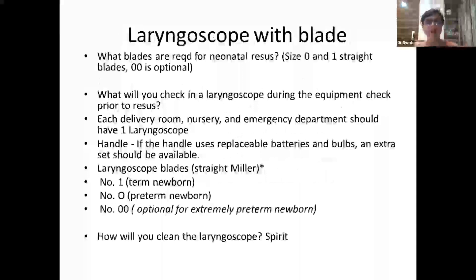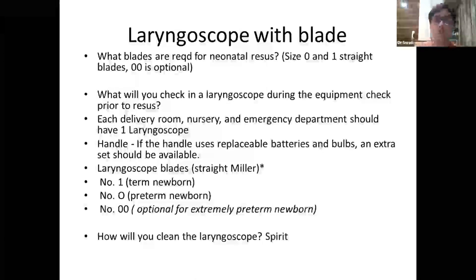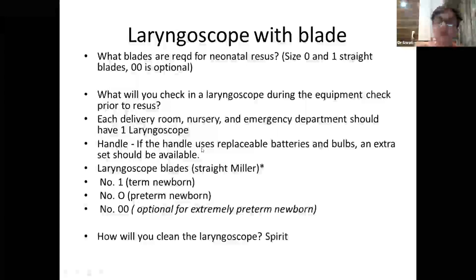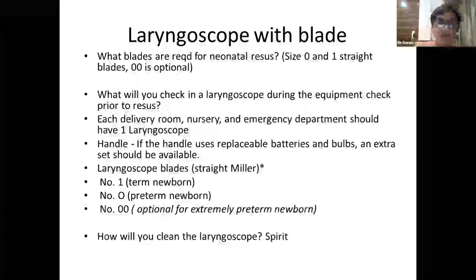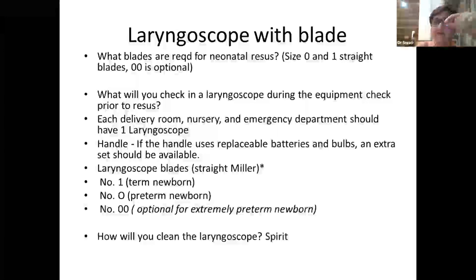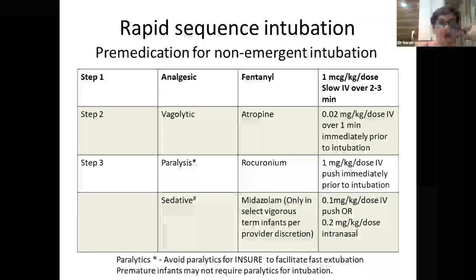For neonatal resuscitation, size 0 and size 1 straight (Miller) laryngoscope blades are recommended; size 00 is optional. Every delivery room, nursery, and emergency department should have a laryngoscope. The handle should be checked, replaceable batteries and extra bulbs should be available, and the correct blade sizes should be on hand. The laryngoscope is cleaned on the outside with spirit only — it should not be dipped in any solution as this damages the internal electrical components.